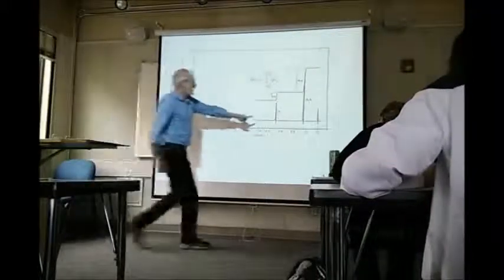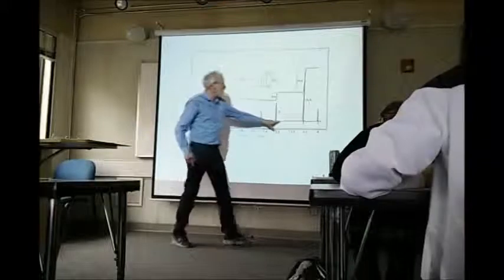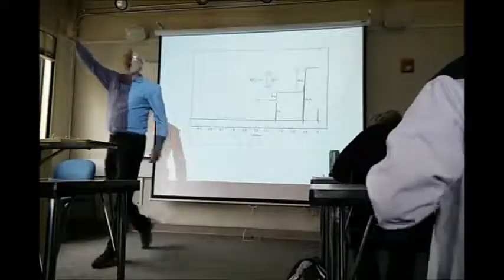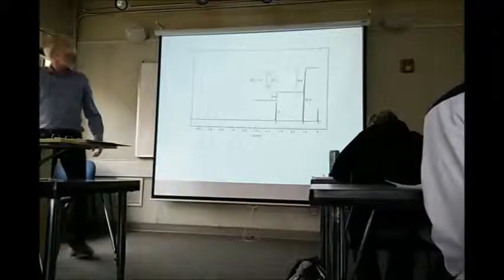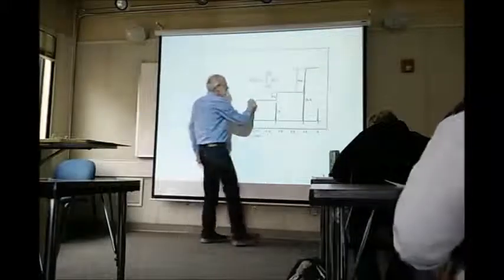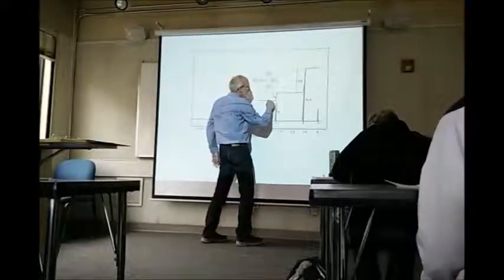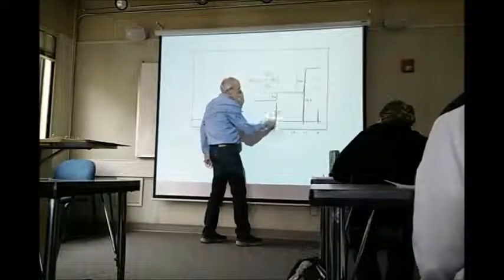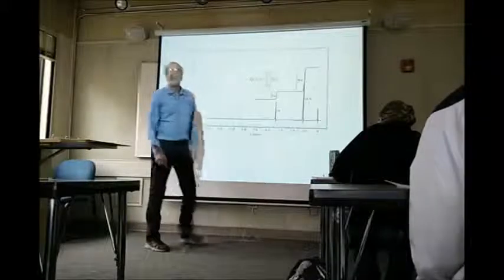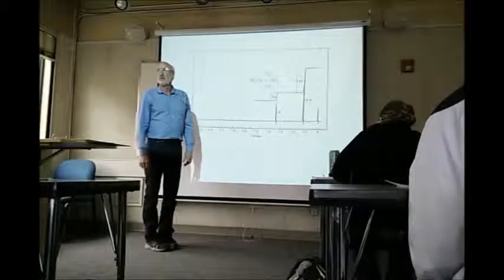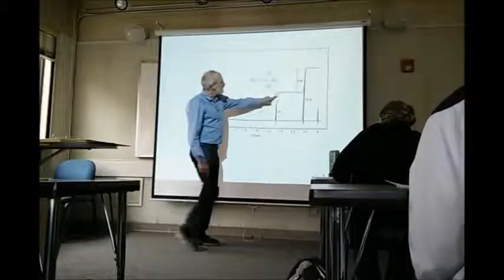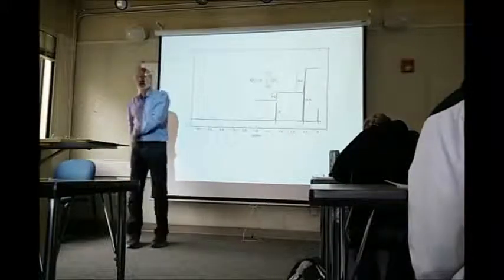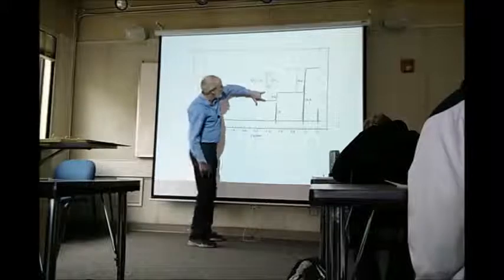This is the NMR spectrum that you normally see. But then what you do is you put, electronically, the spectrometer into integration mode. And what it does is it goes along flat, and when it comes to a peak, it goes up proportional to the area under the peak. So this is the integration curve. It doesn't tell you the exact area, just the relative area. So you measure that height.